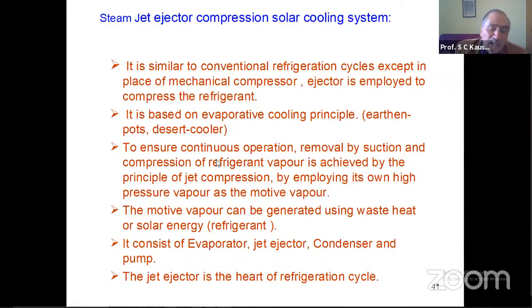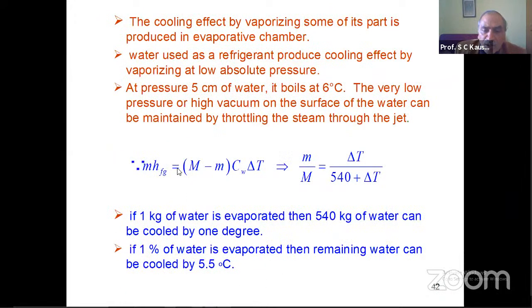In mechanical compression, 70% of the cost of the system is because of the compression. Here, the cost of the ejector compression is very low. That is why this system is very desirable for industrial air conditioning options. The latent heat of vaporization and the temperature drop of the remaining water can be simply calculated by the heat balance equation. If 1 kilogram of water is evaporated, then 540 kilograms of water can be cooled by 1 degree centigrade.